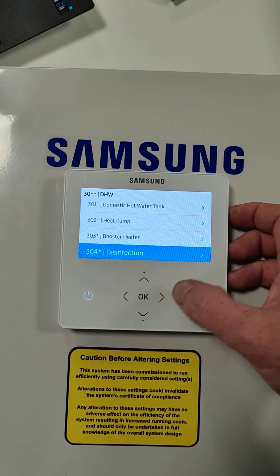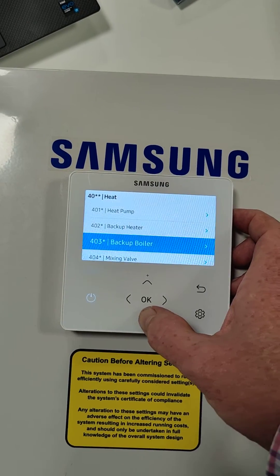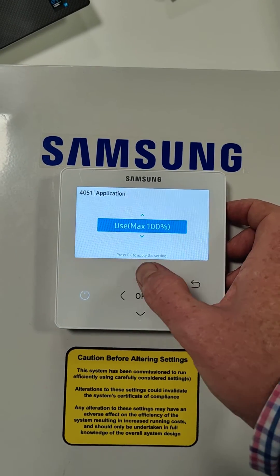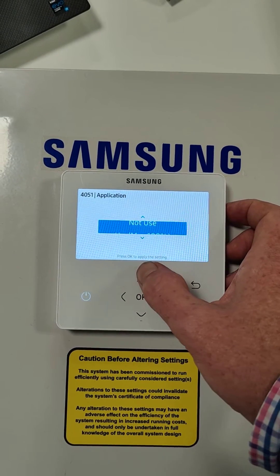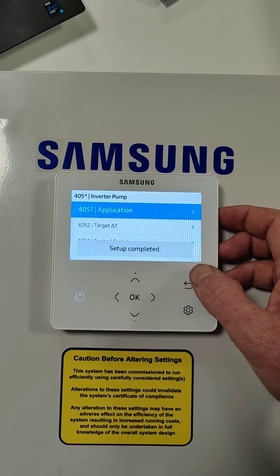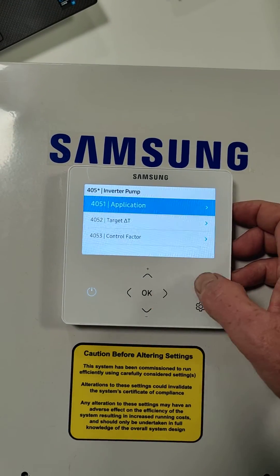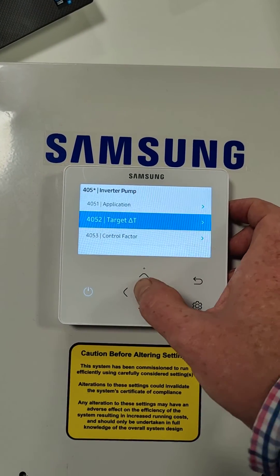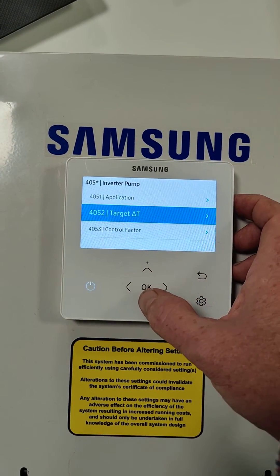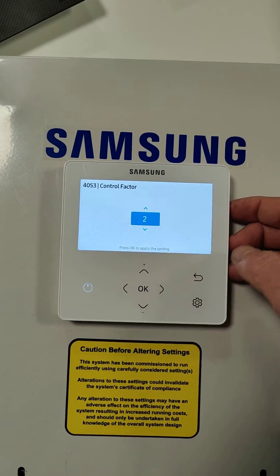Then we're going to go back again and go to 40 five, and we're going to go to 4051, which is inverter pump. So we are actually going to use the inverter pump here, and let's set this to use 100% — this will tell the unit that it's got a PWM pump. You can check these if you like: target delta T should be 5, so this is the pump speed modulation, and the control factor — I'm not sure what this does, but we've left it on 2.